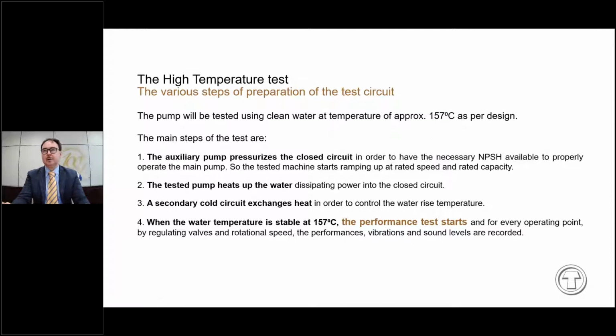The test has a setup procedure of 4 points. The first step is to pressurize the circuits in order to have the required NPSH to correctly operate the pump. When the circuit is pressurized, we can start up the boiler feed water pump in order to increase the fluid temperature by dissipating the mechanical energy. So the fluid temperature rises, and we can regulate it with the heat exchanger. When the temperature of the water is stable at 157 degrees in this case, or at the desired temperature, we can start the real performance test and check every operating point by regulating valves and rotational speeds.